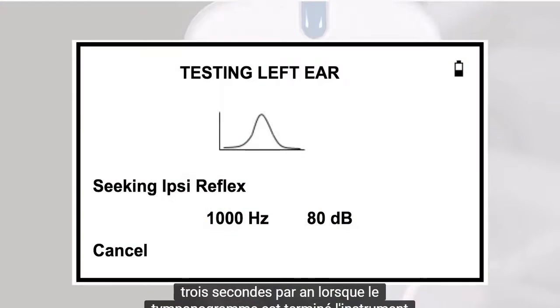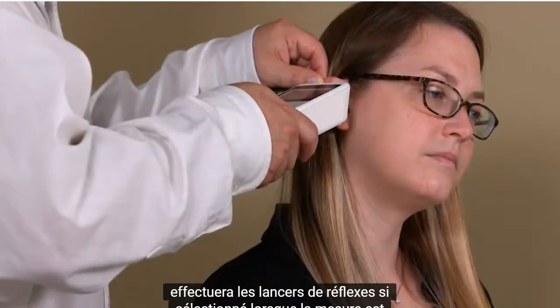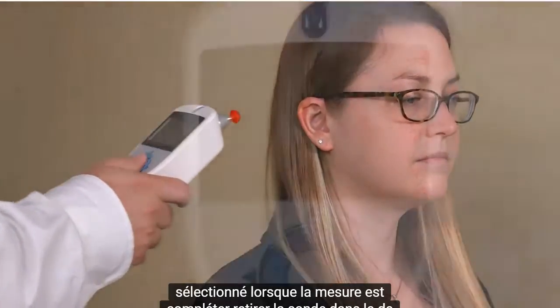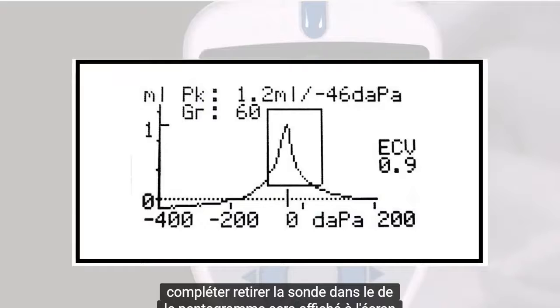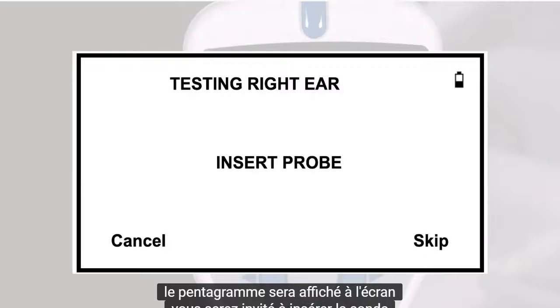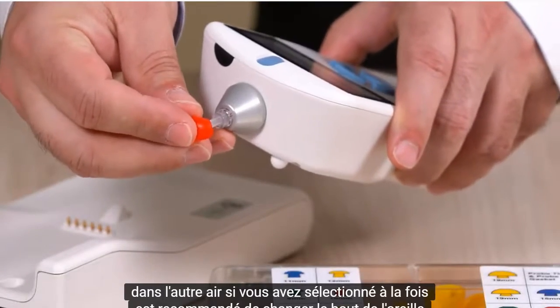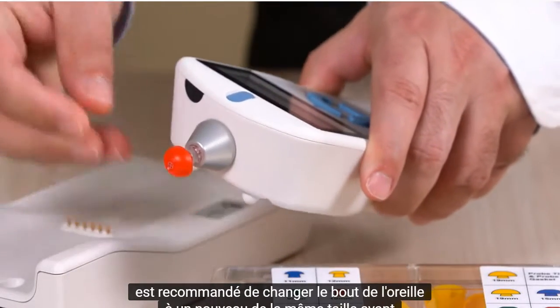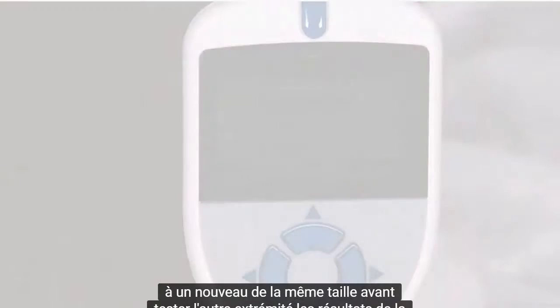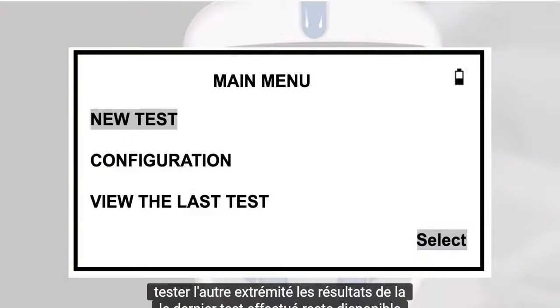When the tympanogram is complete, the instrument will perform the reflex tests if selected. When the measurement is complete, withdraw the probe and the tympanogram will be displayed on screen. You will be prompted to insert the probe in the other ear if you selected both. It is recommended to change out the ear tip to a new one of the same size before testing the other ear. The results of the last test performed remain available even if the MicroTymp 4 has been turned off.